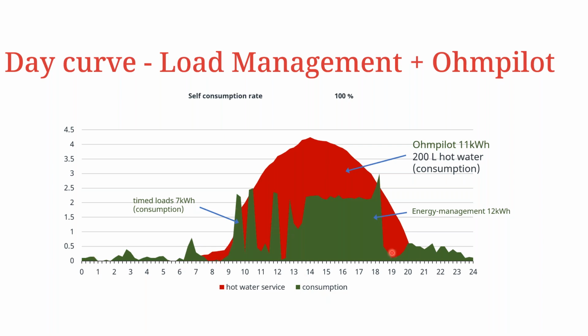So you can see here that we are able to generate the hot water that is required for this particular family within the period whereby we have PV production, and therefore using this kind of concept, you are able to offset what would be typically a lot of PV production or consumption from the grid.